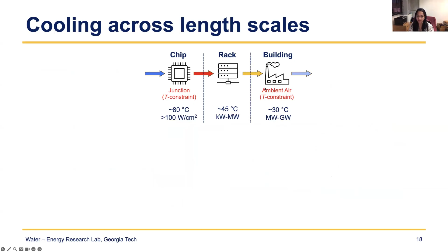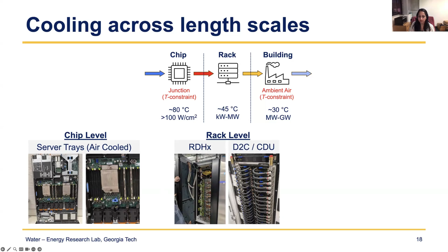So typically, these are what's conventionally used. For your servers at the chip level, you can have just air cooling, but now it's become direct-to-chip liquid cooling using cold plates. At the rack level, you can have rear door heat exchangers, which are mostly for air-cooled systems, but now we're looking at coolant distribution units where you have liquid loops going to each server tray. And then at the facility level, traditionally, it's been a lot of cooling towers where you have to evaporate large amounts of water.